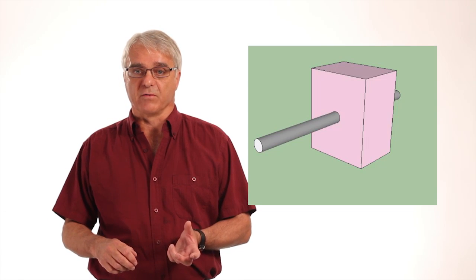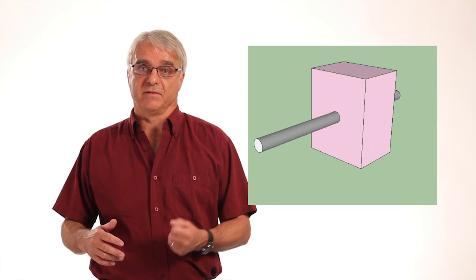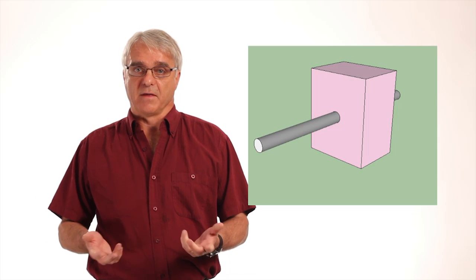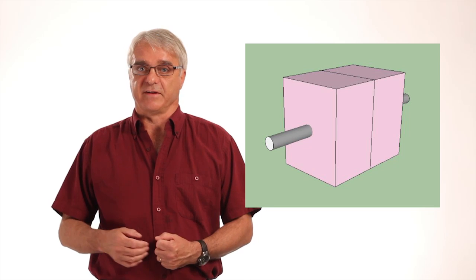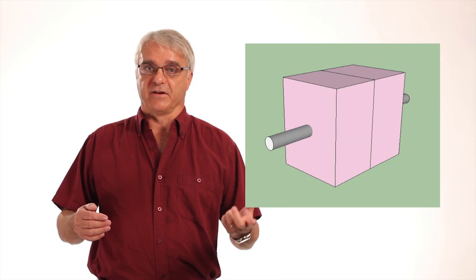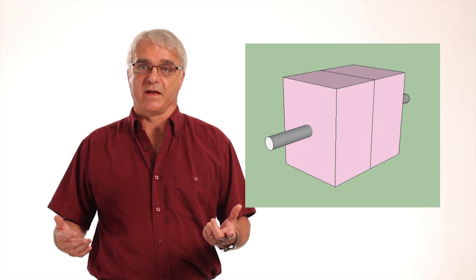If I had an area of insulation and then I had a steel rod going through it, I might have 10 units of heat flowing through the insulation, but easily 10 going through the rod. That's bad enough, but now if I double the insulation and I think I'm improving things, I've only changed the insulation down to 5 units, but I still have the 10 going through the rod.